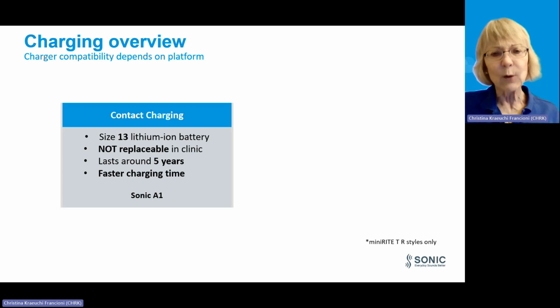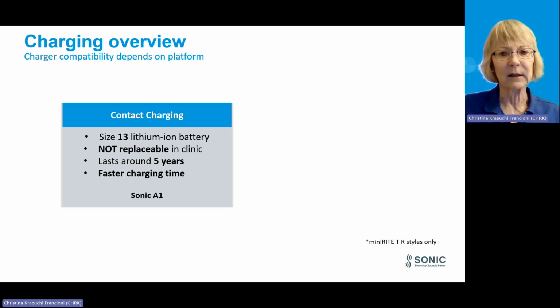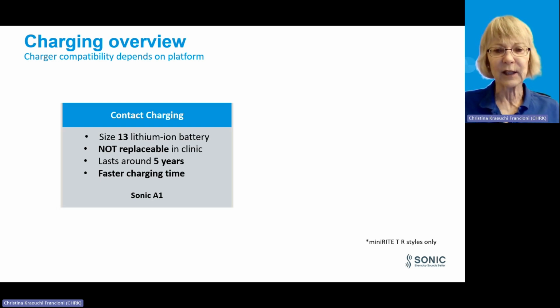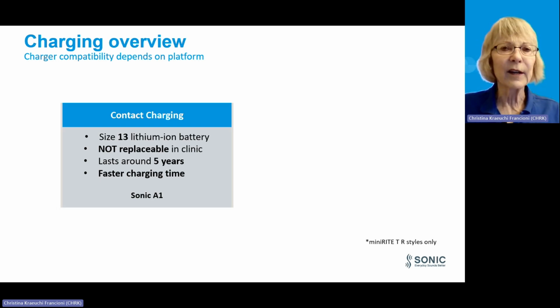Contact charging for hearing aids uses a unique constant capacity charging technique, which reserves part of the battery's initial capacity to provide a more stable battery performance throughout the lifetime of the hearing aid. This helps to offset some unavoidable battery degradation that will occur over time, allowing the battery to last longer. Because the battery is fully integrated into the instrument, it cannot be replaced in the clinic. However, the need to replace it outside of a repair service would be rare, considering that it should last around 5 years. The overall benefit of going to contact charging for Sonic is that we can provide the user first with faster charging and then with a longer battery life.